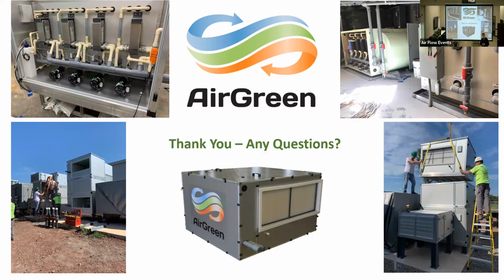Super. Yes, sir. So with the system, we don't have to cool it down to the dew point, is that correct? Correct. So there's no saturated air in the system, so do we need to worry about the drain or water in the system? No, we are capturing it all into the desiccant solution, and then the regenerator is putting it into the exhaust air or outside air streams. So there is no condensation to deal with.